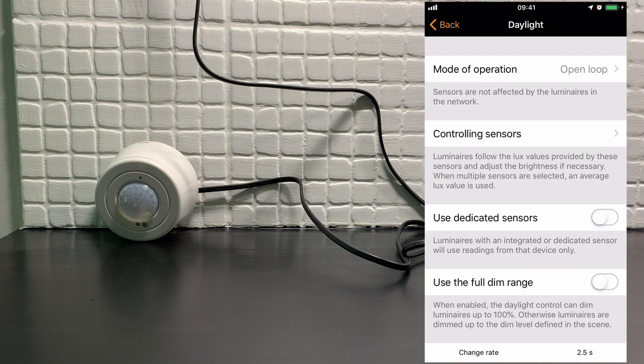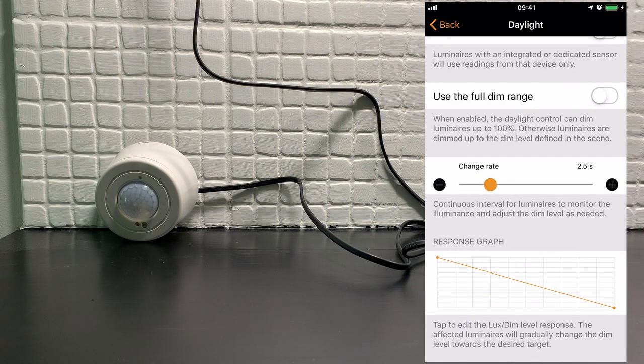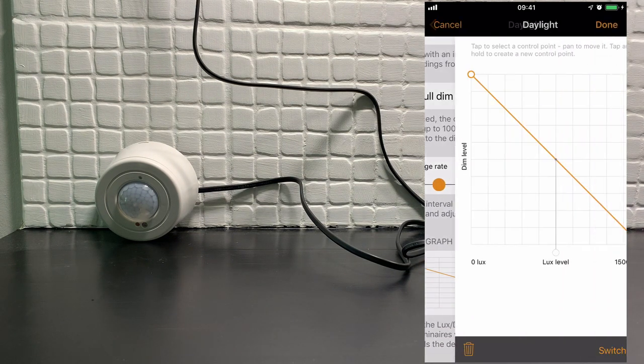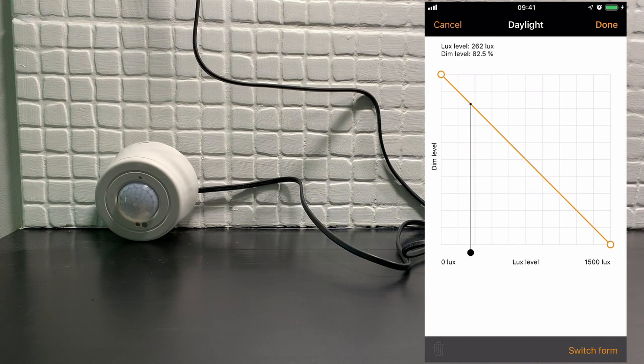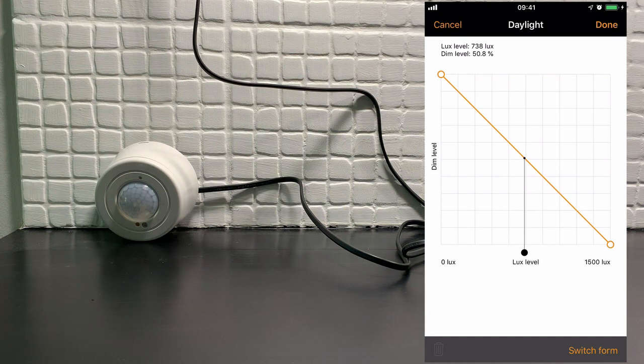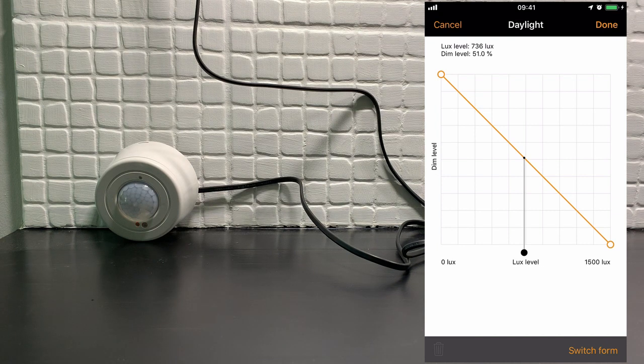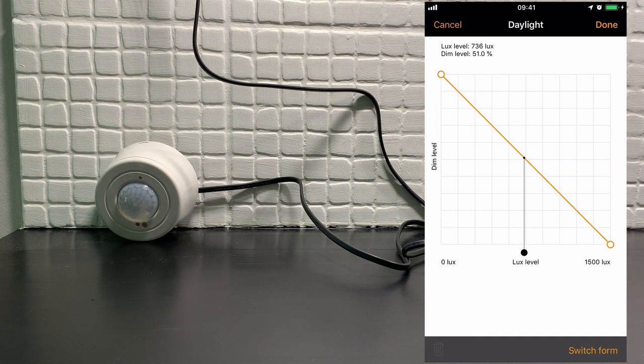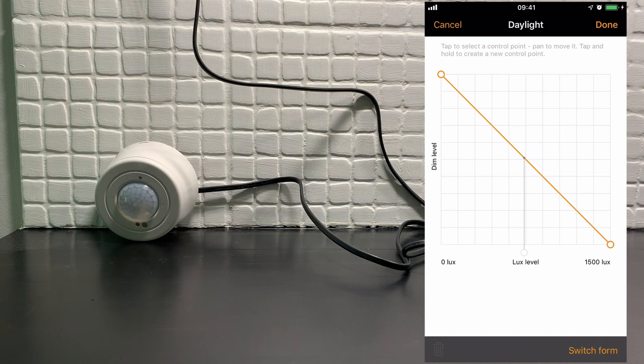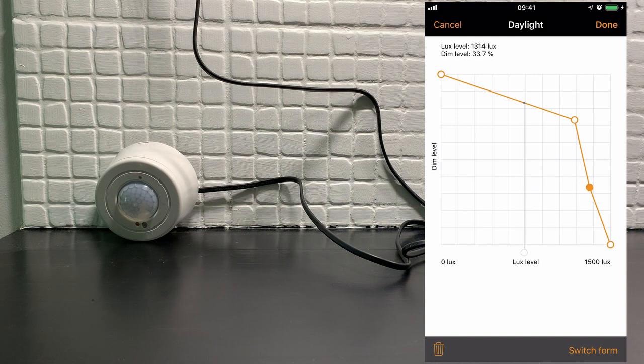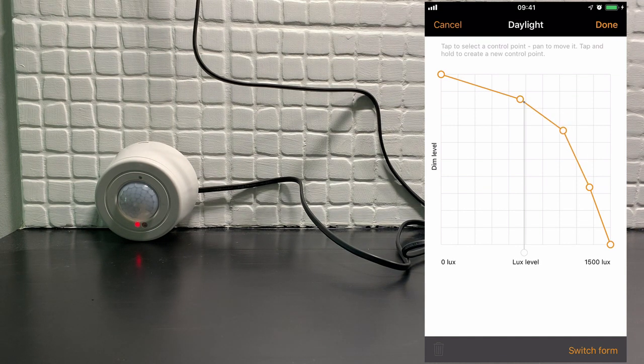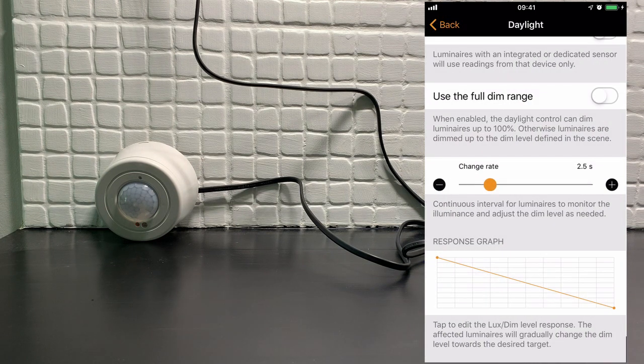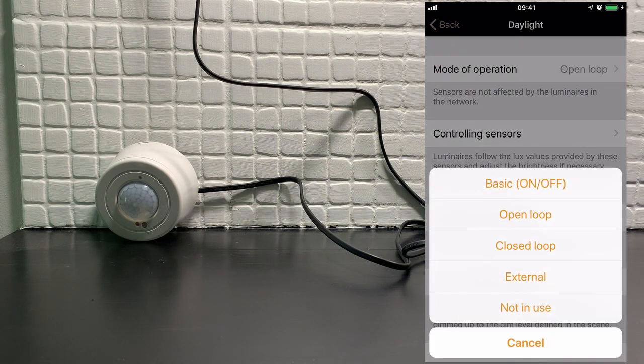An open-loop allows you to define a graph based on the amount of lux being read by the sensor. So from this example here, at this particular position, when the lux sensor is reading 736 lux, it will dim the levels of the luminaires down to 51%. And as usual, you can change this graph however you want to.